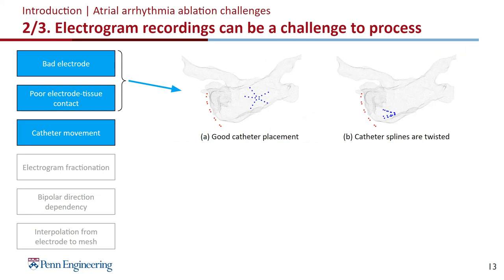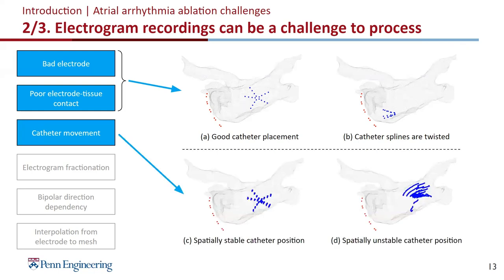The other challenge is that electrogram recordings are not easy to process. Figure A shows a good catheter placement where all splines are spread out. But in figure B, the splines are twisted and can cause electrodes to collide, creating noise. Another problem is catheter movement: figure C shows a stable catheter position during recording, held for 2.5 seconds. But in figure D, the catheter has a very large movement — the problem is it will no longer record the same location, so the recording has no meaning.